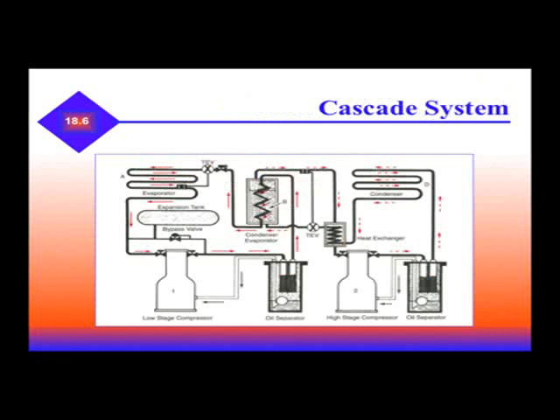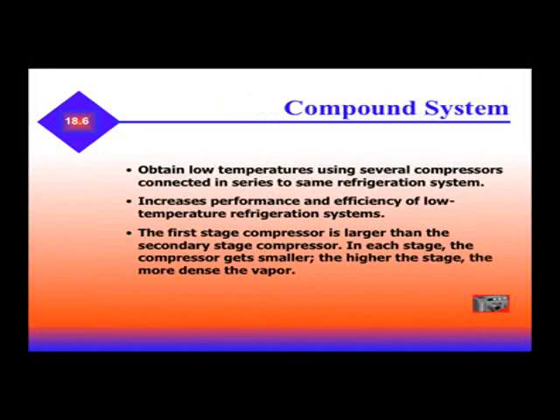We have our low stage and high stage, separated by a heat exchanger. The evaporator of your high stage unit cools the condenser, which is actually the condenser of the low stage compressor. The compound system obtains low temperatures using several compressors connected in series to the same refrigeration system, increasing performance and efficiency of low temperature refrigeration. The first stage compressor is larger than the second stage compressor; in each stage, the compressor gets smaller. The higher the stage, the more dense the vapor.